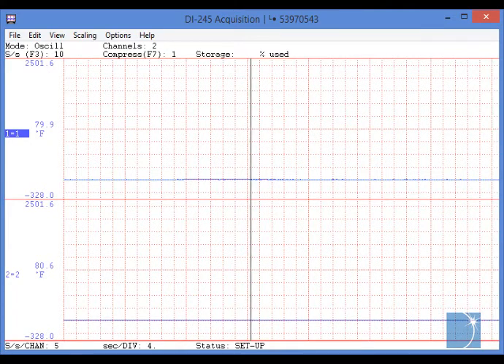Note that the temperature on channel 1 displays just a 0.4 degree offset, equivalent to 9 microvolts. Channel 2 displays an offset of about a half a degree. In the DI-245's $75 per channel price range, that type of common mode and crosstalk rejection is unheard of.